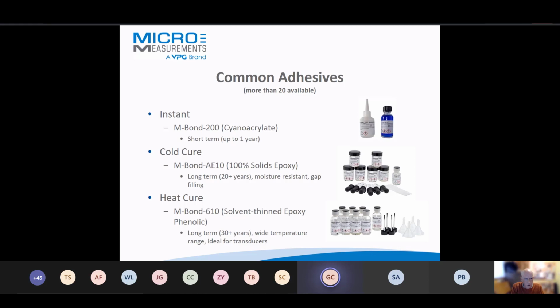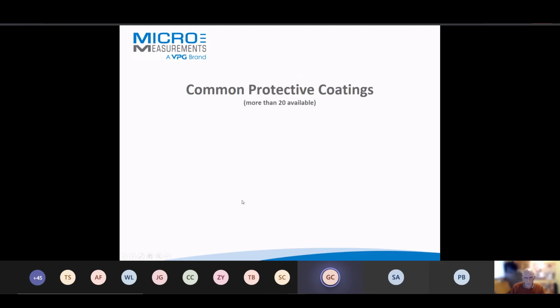And then if you want the ultimate performance, heat cure adhesives, something like M-Bond 610 - almost every commercial load cell you purchase will be using this adhesive to hold the gauges down. 30 plus years, in fact one of our divisions has now got an MTBF of 50 years using our strain gauge adhesive. So really good if you want the widest temperature range, the longest life, -269 to about +370, so very wide ranging temperature as well. Used a lot in superconducting magnet type applications for that cryogenic capability.